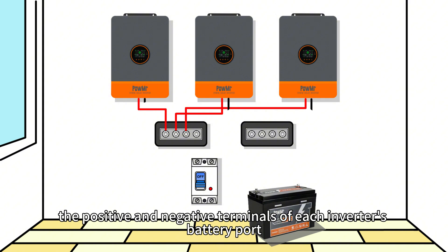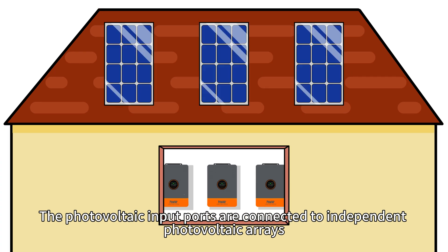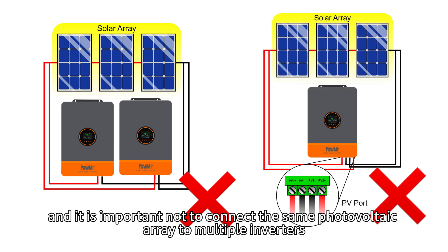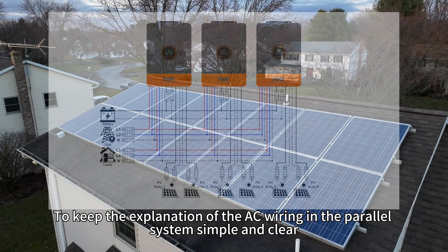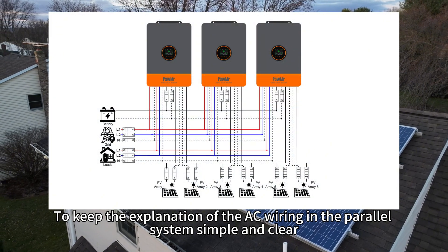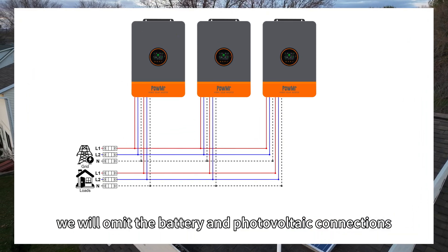In the power system, the positive and negative terminals of each inverter's battery port are connected to the battery. The photovoltaic input ports are connected to independent photovoltaic arrays, and it is important not to connect the same PV array to multiple inverters. To keep the explanation of the AC wiring simple and clear, we will omit the battery and photovoltaic connections.